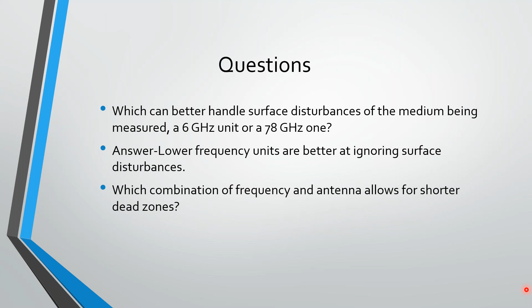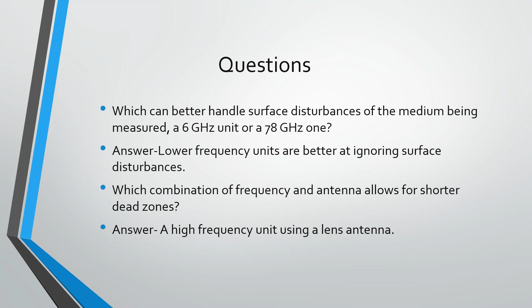Which combination of frequency and antenna allows for shorter dead zones? And again, that dead zone is that little bit of area up there at the top where, if the fluid or the medium gets too close, we basically stop measuring at that point. And we mentioned that higher frequency units can use a lens antenna, right, which is a shorter antenna, thereby allowing us to have shorter dead zones.